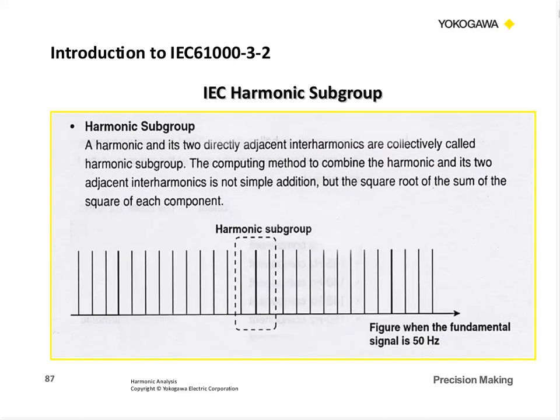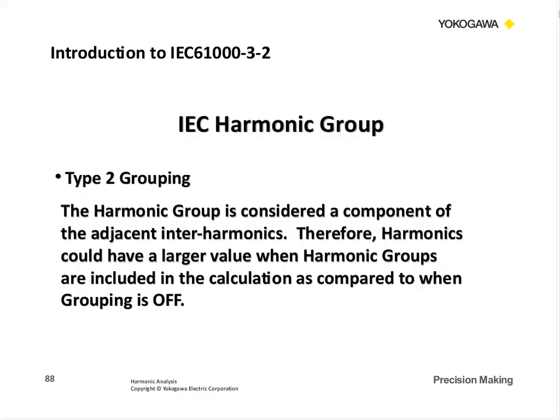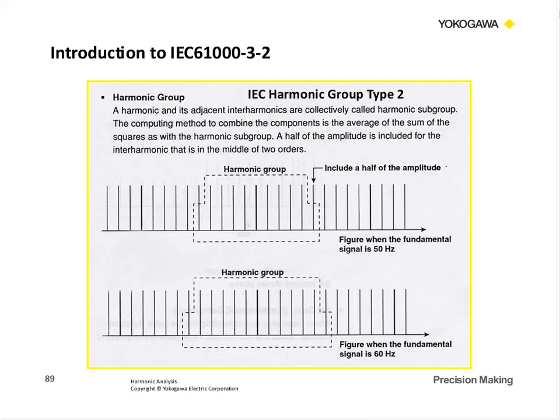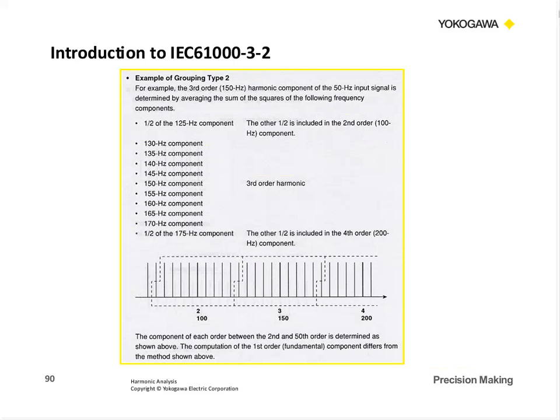Then we get into part of the grouping and the subgroups, where we look at an integer value and look at one harmonic, subharmonic on each side. So again, we're talking about the grouping of the IEC measurements. And this is just so that, if you hadn't heard of it, you'll have an idea of what these are. So again, some other ideas on the grouping and the various frequencies that they combine together to calculate the THD.